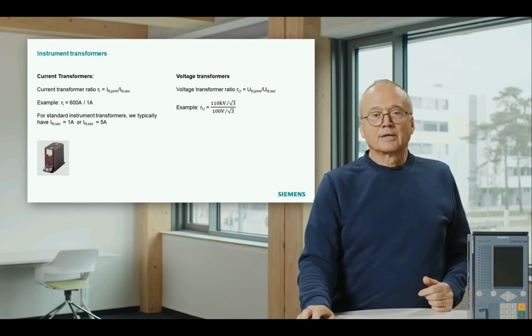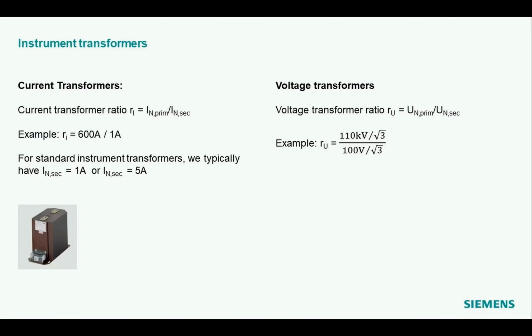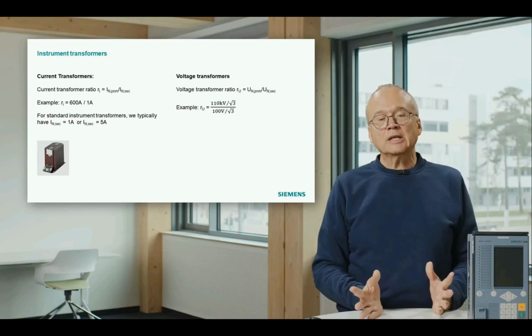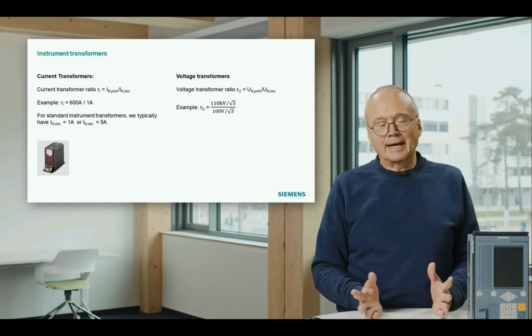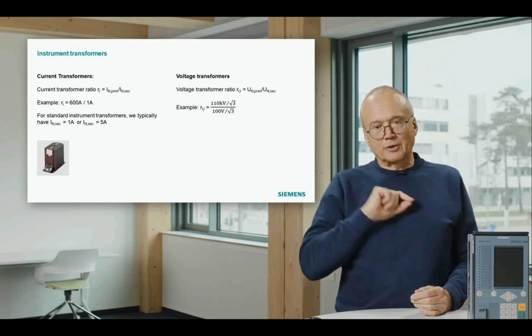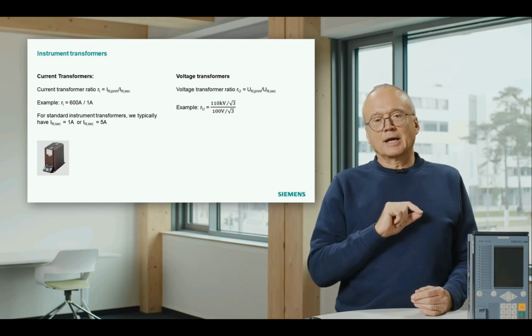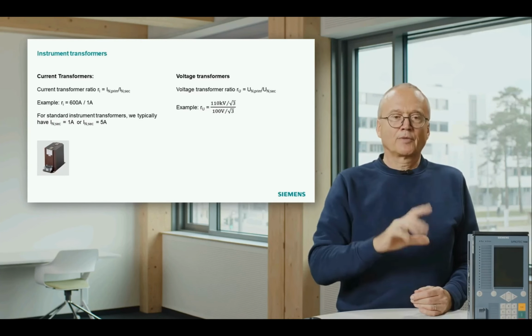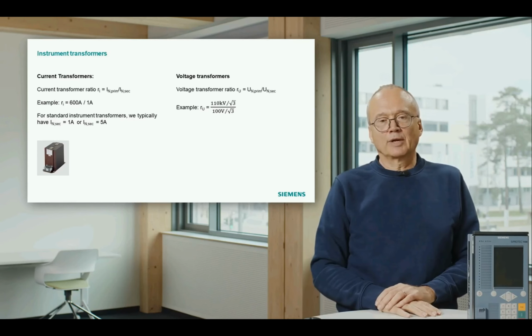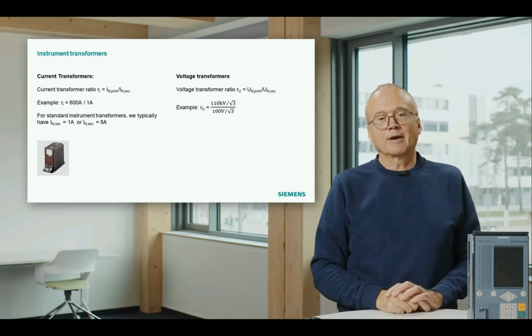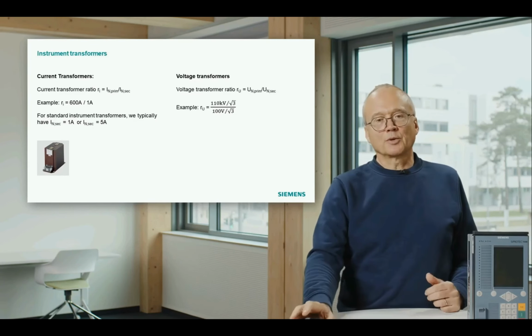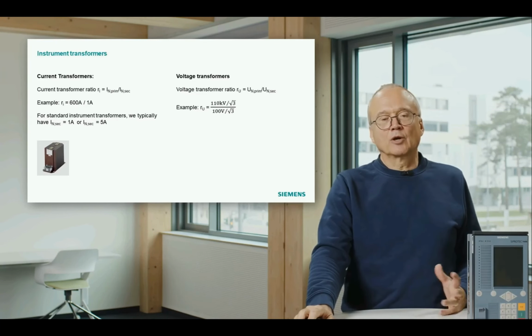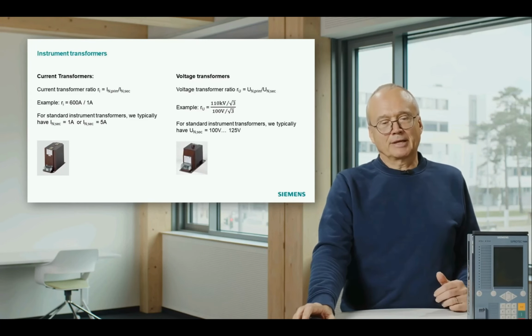On the voltage transformer side, we have typically, here's an example, 110 kilovolt divided by square root of 3 to 100 volt divided by square root of 3. Where does the square root of 3 come from? If you have a 110 kilovolt line, the 110 kilovolt is the voltage between the 2 phases. The voltage transformers are normally connected from phase to earth. That means the voltage they see in normal operation is in this case 110 kV divided by square root of 3. Same applies to the secondary side. It is normally something around 100 volt, also there divided by square root of 3.